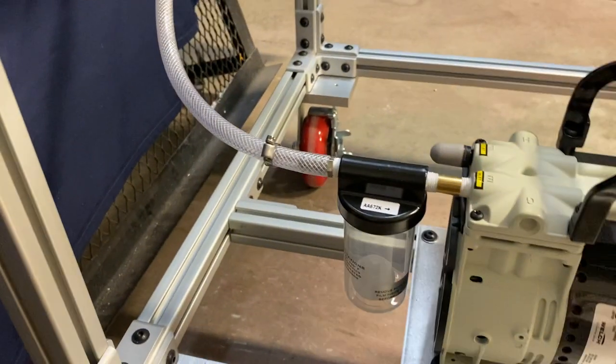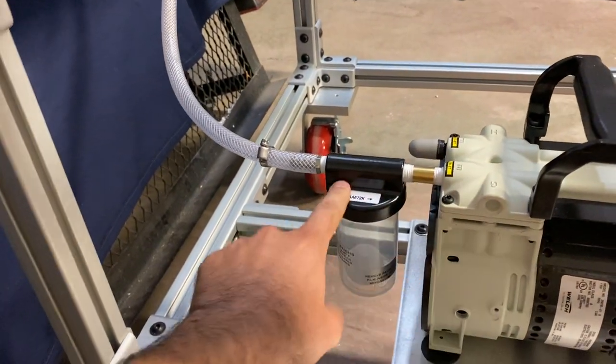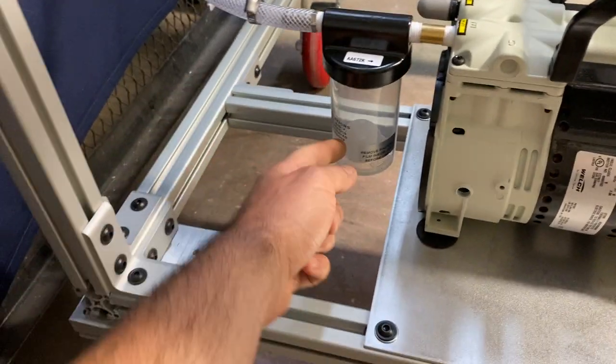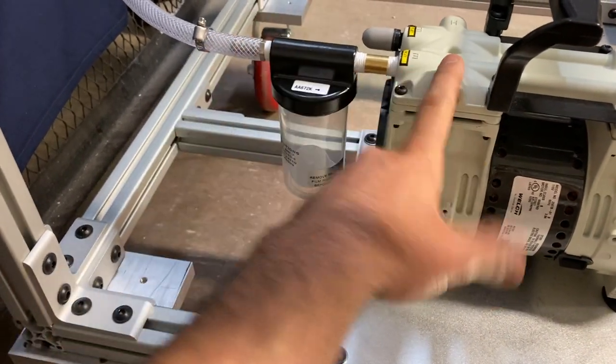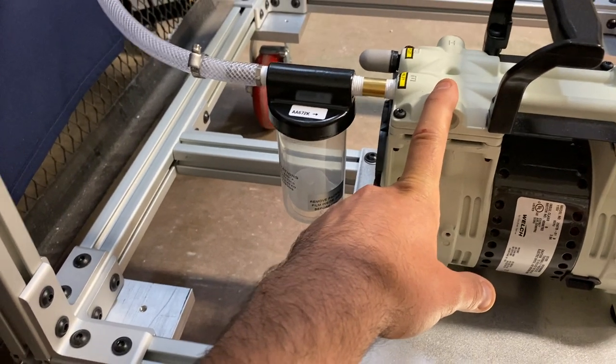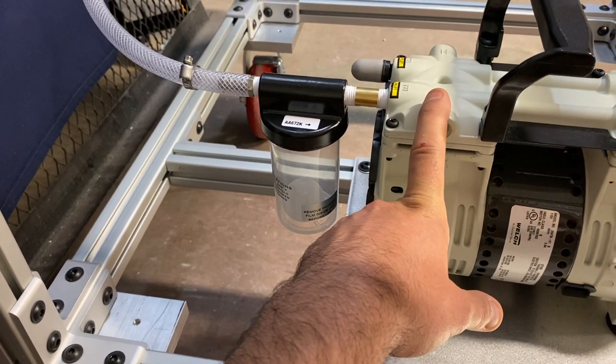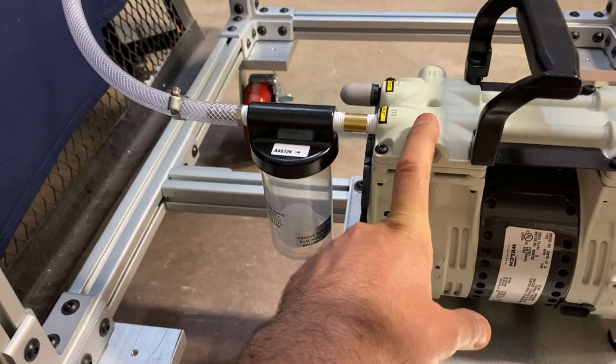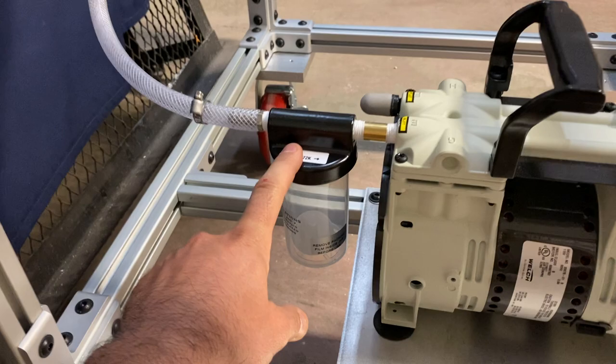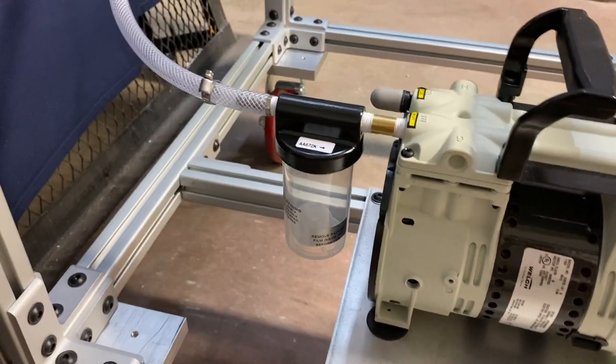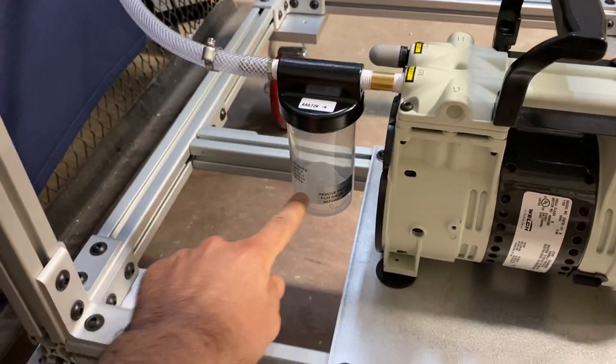and then the water starts going down this vacuum line into this pump and if you didn't have this vacuum pump protection valve what would have happened is you get water straight into the vacuum pump and then that's it you are fried, especially if you have a rotary vane vacuum pump.